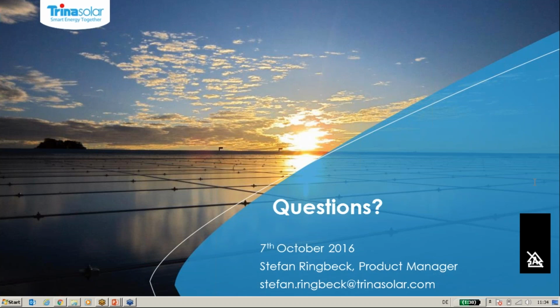There's a question about shading. There I need to say it clearly depends on the module orientation what the shading will be. For example, if you mount the module in landscape, then you only impact one substring, and if you install them vertically, so portrait, then you will impact the complete module. But the impact will be quite similar because it's basically the same mechanical layout.